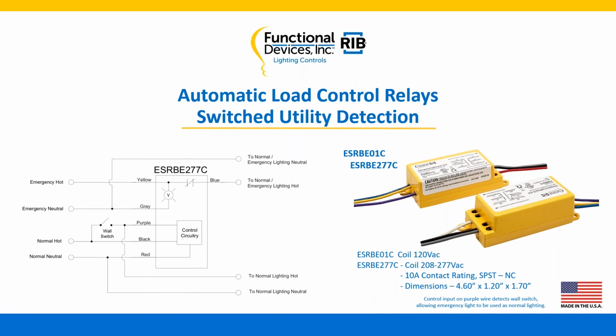Again, this is an ESRBE01C and an ESRBE277C. Coil of 120, 208 through 277, pretty standard in the lighting world. This is a 10 amp contact rating, single pole, single throw, normally closed. I mentioned the dimensions here, 4.6 by 1.2 by 1.7. Early on, this was the design we did. It played out very well for us, but what we decided to do was move on, and I'll show you a little bit down the road.